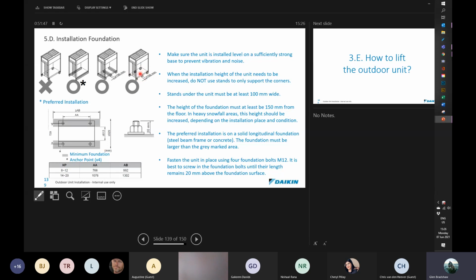The reason for this is that the middle of the unit, that's where the compressors tend to be, that's where the weight is in the unit, and you need to make sure that it doesn't sag in any way, because it pulls the panels out of alignment and causes the unit to generate quite a bit of noise. It is a requirement to bolt units down, and believe it or not, we've had 300 kg condenser units blown over in the wind in Cape Town. Quite something to go and see when you get up on a roof and find a condenser lying on its side, and the end result of that was 2 compressors that were damaged because they pumped their oil out. All right, so take note of that. Units must be bolted down.